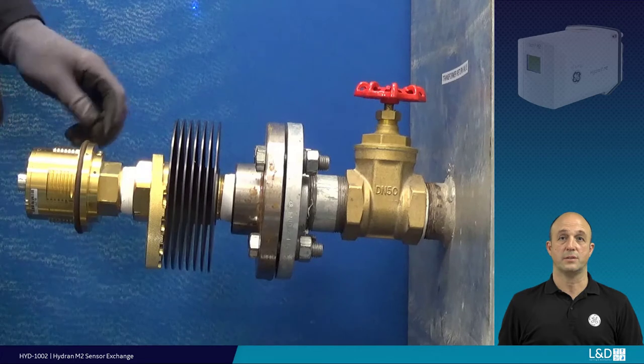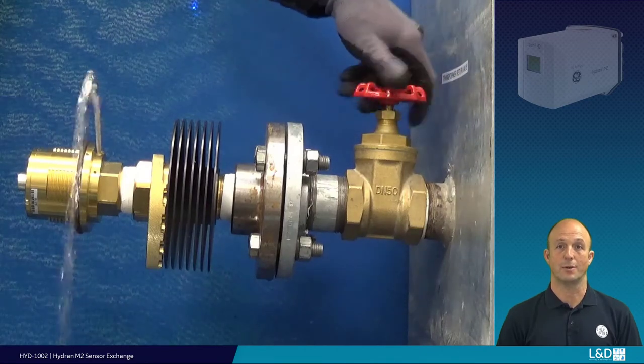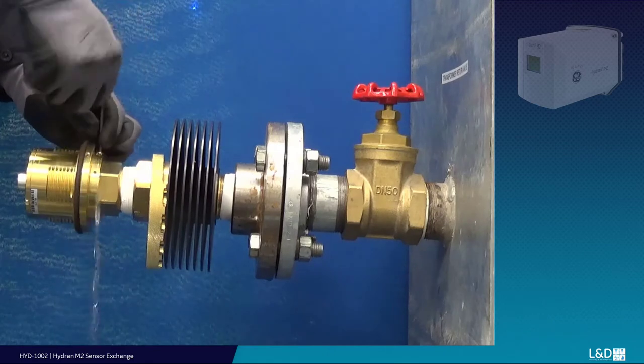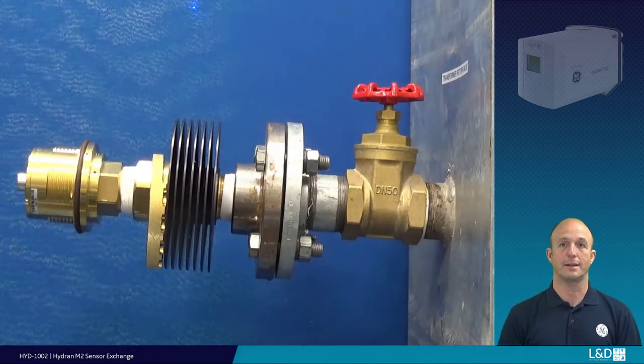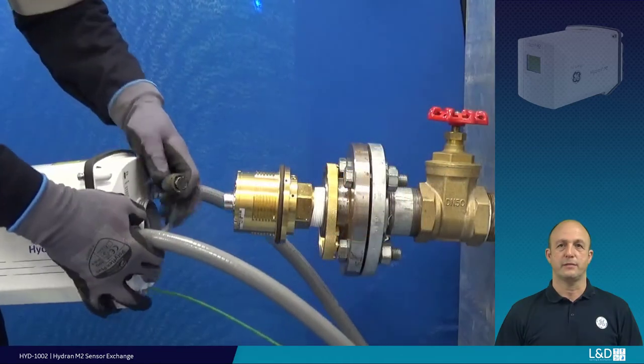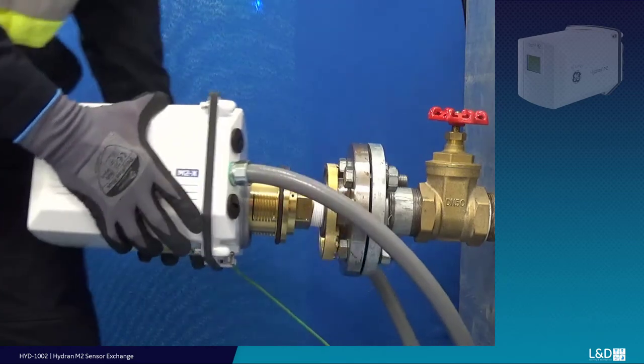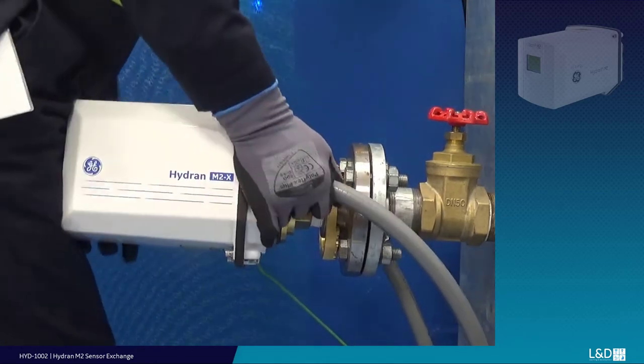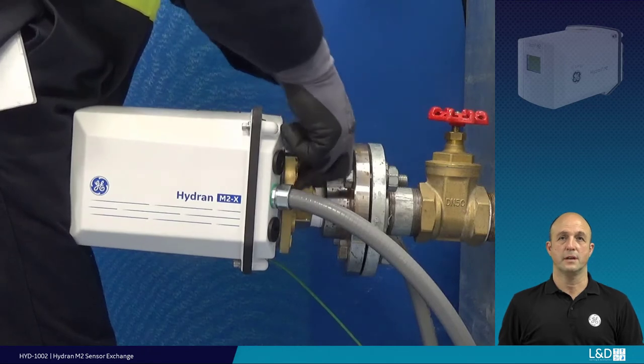Ensure a suitable container is in place to catch the waste oil. During bleeding, ensure you fully open the supply valve to allow unimpeded thermal oil flow. When this is complete and air-free, close the bleed screw and clean down the sensor and electrical connections. Relocate the device and reconnect the cable quick-connect, remembering to align the keyway. Now slide the device back over the sensor, ensuring it is fully located over the sensor o-ring.